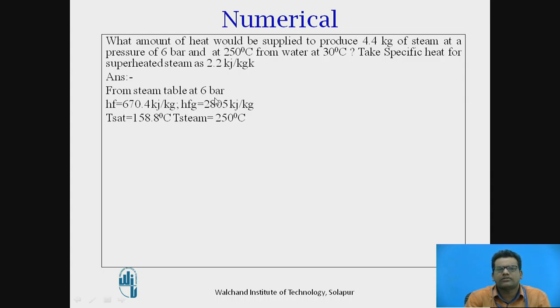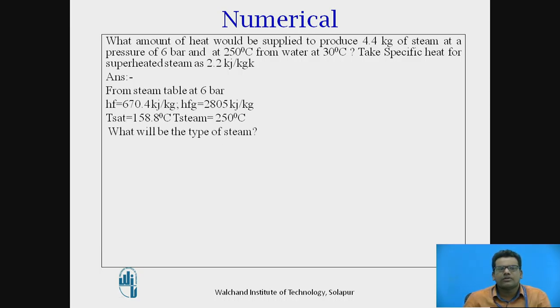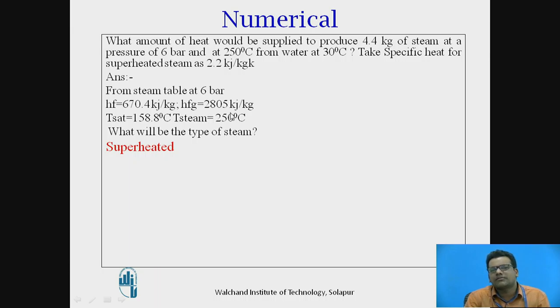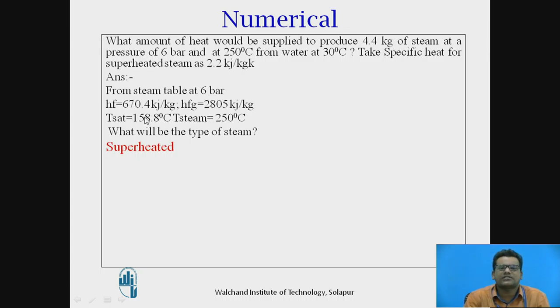From the steam table at 6 bar: HF = 670.4 kJ/kg, HFG = 2805 kJ/kg, and saturation temperature = 158.8°C. The steam output temperature is 250°C. Since the output temperature (250°C) is greater than the saturation temperature (158.8°C) at 6 bar, the quality of the steam is superheated, meaning X = 1.